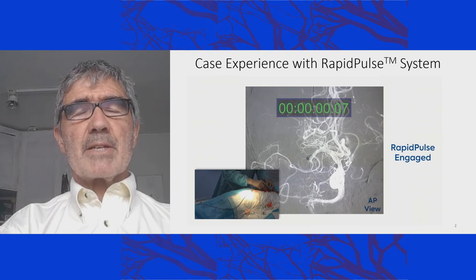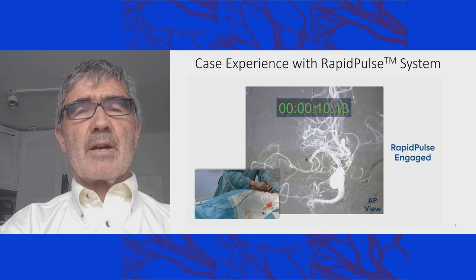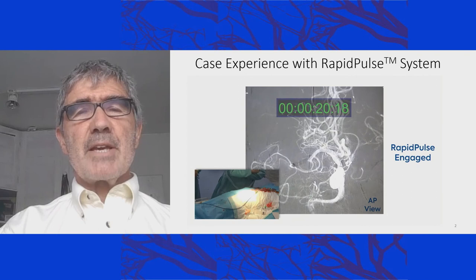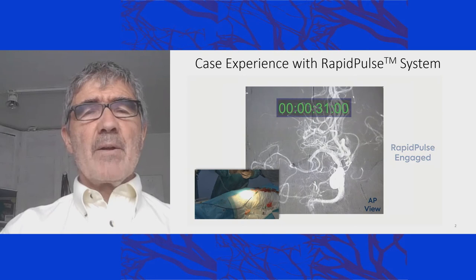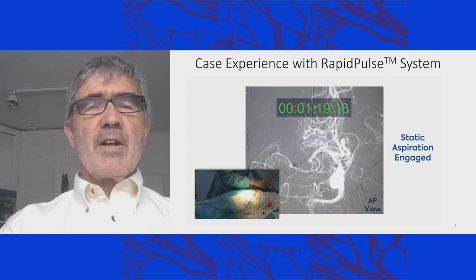You can see the movement of the aspiration catheter — ba-ba-ba-ba — this is the Rapid Pulse system changing the vacuum eight times per second, as I described. This gives mechanical forces that destroy the clot structure.